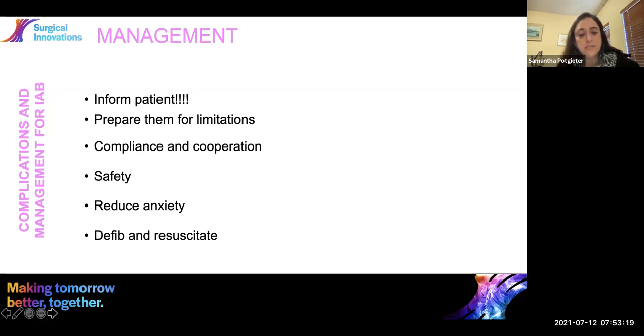I've put in there the defib and resuscitate because it's a question that we often get. Do you have to switch the pump off if you are resuscitating, or if you do shock the patient? No, you don't. Just don't hold on to the console if you are in fact going to shock the patient, because it will shock you. So you don't need to switch off the pump if you are doing a resus, but you will find that the pump is going to alarm, and it is going to indicate that the augmentation isn't good and that the patient's blood pressure isn't good. And so all the triggers that it's looking for is problematic during a resus. But you don't need to switch off the console, and you don't need to stop it.